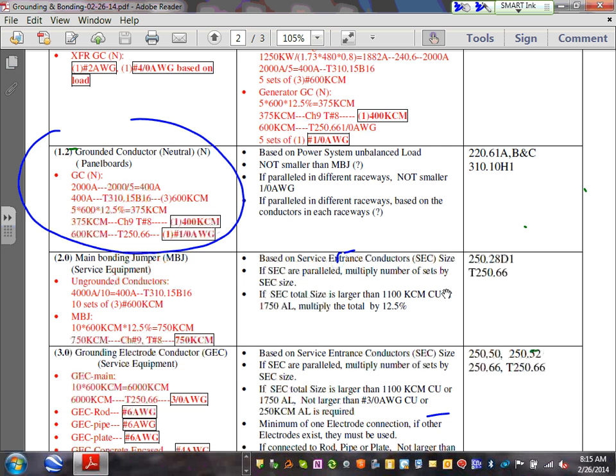You guys know, right? You parallel. So I decided to parallel 5 sets. Divide by 5, that gets you 400. Take the 400 to 310.15(B)(16). That will get you 3 conductors, 600 kcmil. Can you guys see that?